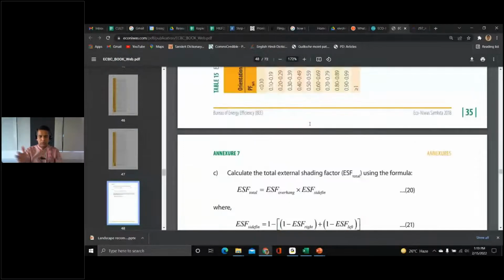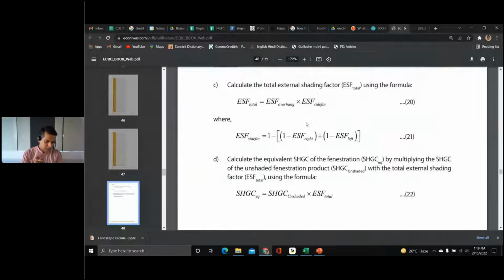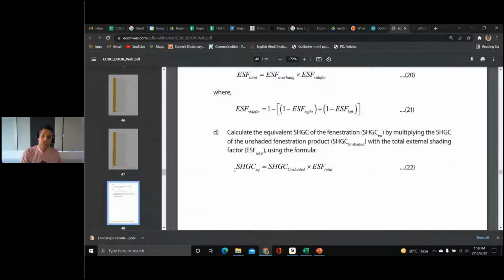And that will give you the answer for the SHGC values. So this is the total SHGC calculation. ESF, external shading factor total, is equal to ESF overhang into ESF side fin. ESF side fin again is divided into right side fin and left side fin. So it looks like a really complicated calculation, but when you do it in Excel it's very, very easy and simple to do. And then you calculate your SHGC equivalent, which means equal to a very stringent SHGC, but because you're shading it, you get a more relaxed SHGC.